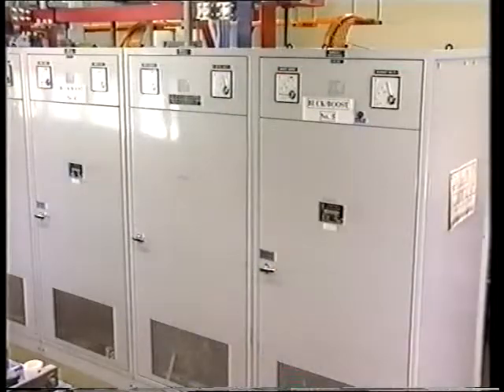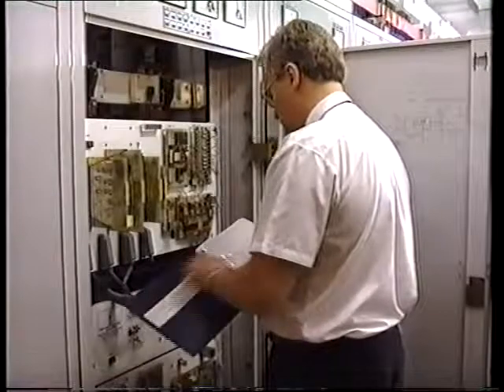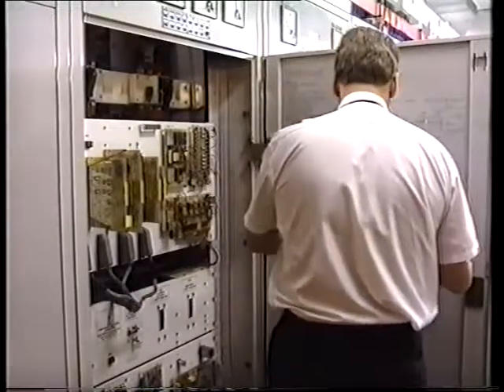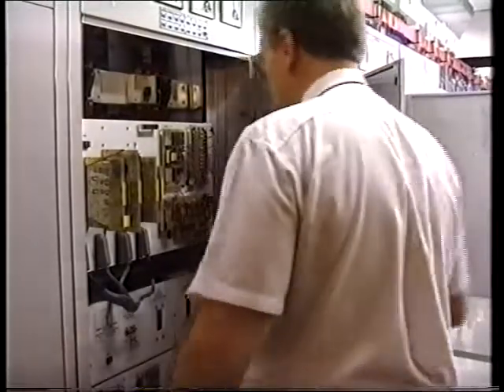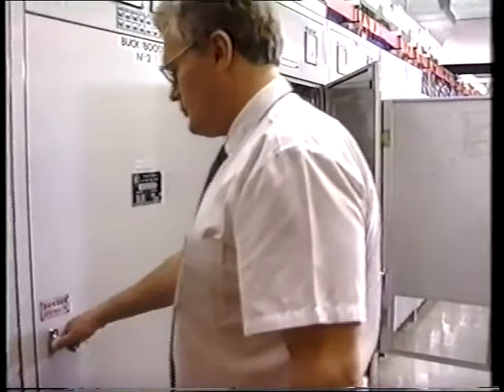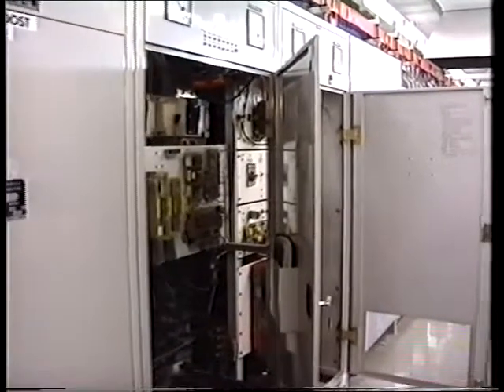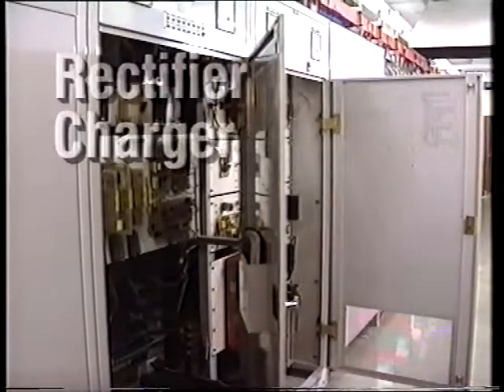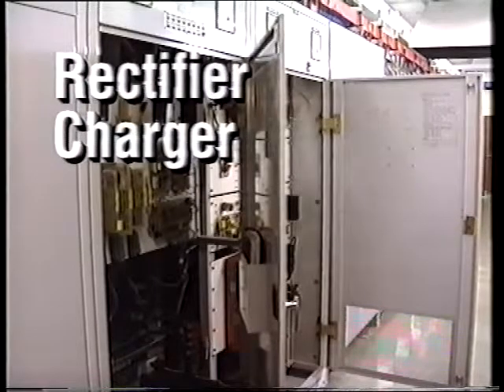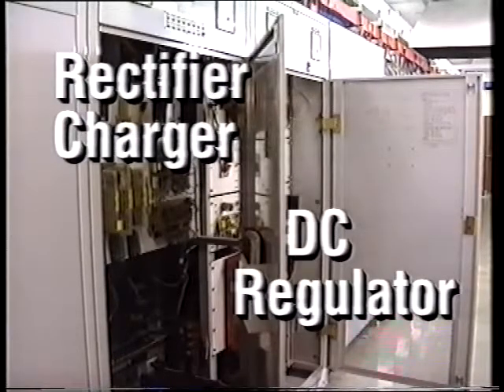Individual power supply units can be found in two maximum load capacities. These are 500 or 1000 amps. The 500 amp power supply is contained in one cubicle only. The 1000 amp power supply consists of two cubicles side by side, where one cubicle is called the rectifier charger and the other the DC regulator.